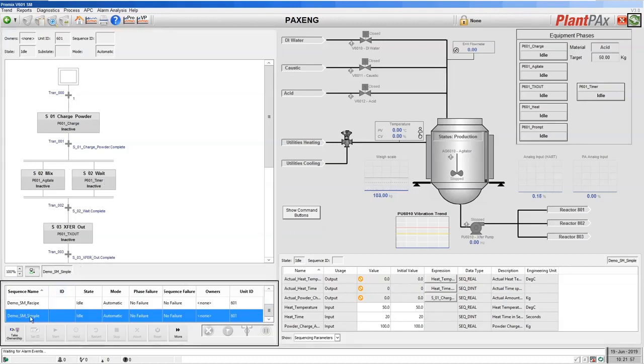If we select the other recipe, we have the details of that recipe and the values that we can run and set. So let's run a recipe. I select my recipe from the control — I need to take ownership. Sequence Manager has a concept of ownership: either an operator can own a sequence from the HMI, or the controller can own the recipe from within the logic.